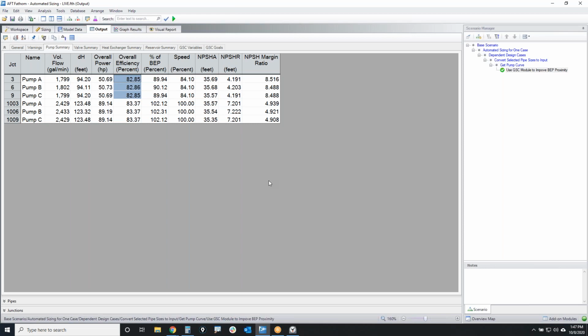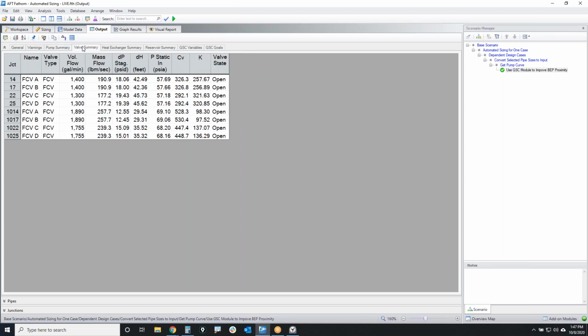So that's pretty good. But when you take a look at these control valves, they're not having to add so much more pressure drop to maintain their set points. And that's a huge deal. That's also going to have a major improvement in your energy cost as well.